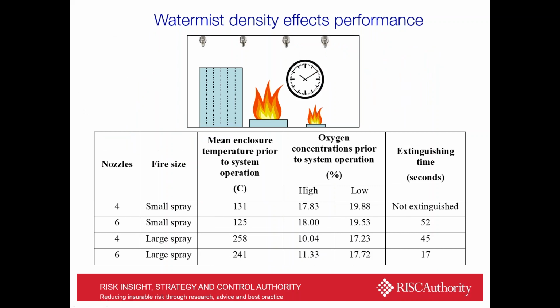Watermist density: I mentioned also that we can change the number of nozzles operating within a compartment in this very well-controlled environment. And you can see there, as we change from 4 to 6 nozzles on small and large spray fires, once again, not surprisingly, the more water you put in, the lower you can drive down the oxygen content of the compartment. And the larger fires do that better.